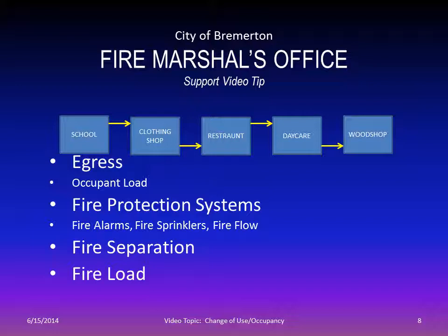Back to an A occupancy, which would have very similar requirements to a school that we started out with, fire sprinkler systems and panic hardware and so on, to a daycare that is going to also have quite a few health department regulations, to a wood shop where we go from a people risk problem to a fire load risk problem. You know, combustible dust and all kinds of flammables, possibly if we have a spray booth or we're painting or doing something like that in there. So this is the transition from occupancy to occupancy and use to different types of uses.